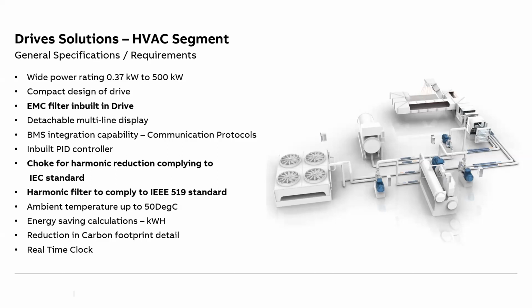So one, you have achieved the desired level of comfort, the desired level of output, and second, it controls your external device, a third party device, by which you can save further energy. So it reduces your chilled water consumption, and this will have a cascading effect, and it will create back pressure on the pump. If there is a VFD on the pump, it will detect that there is a high pressure, so it will reduce the pump flow, and the cascading effect goes up to the chiller also, so you can reduce the chiller output also. So that is how we can achieve automation as well as the next level of energy saving.